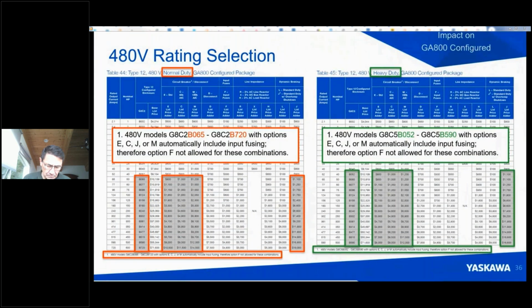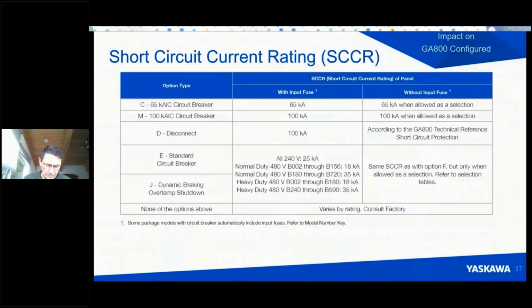And in addition to that, we also try to clear things up because we are asking you to know what your available fault current is in the job you're trying to apply a package to. So we're helping you up front by listing, for some very common combinations of our packages, what the SCCR rating is so that you can make your proper selection on the front end. Either you would have to overshoot and say, I always need 100,000 amps because I don't know, but that will be forcing you into a more expensive package. So the best thing is to know what the customer's available fault current is and match it up with purchasing equipment that has an SCCR rating that is adequate but not overkill. Okay, so we try to help you with that by making note of that in our documentation.